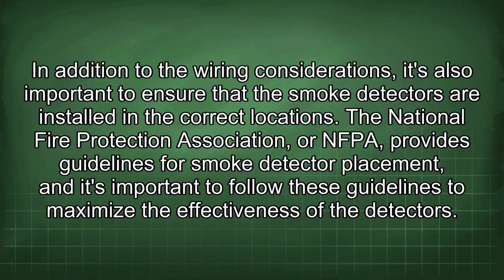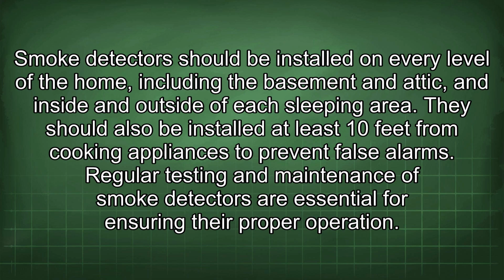In addition to the wiring considerations, it's also important to ensure that the smoke detectors are installed in the correct locations. The National Fire Protection Association, or NFPA, provides guidelines for smoke detector placement, and it's important to follow these guidelines to maximize the effectiveness of the detectors. Smoke detectors should be installed on every level of the home, including the basement and attic, and inside and outside of each sleeping area. They should also be installed at least 10 feet from cooking appliances to prevent false alarms.